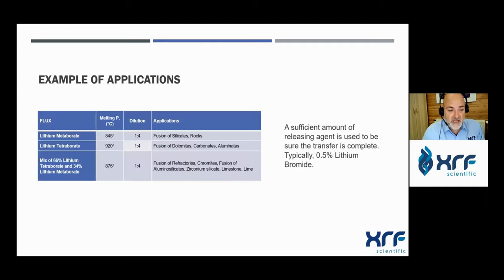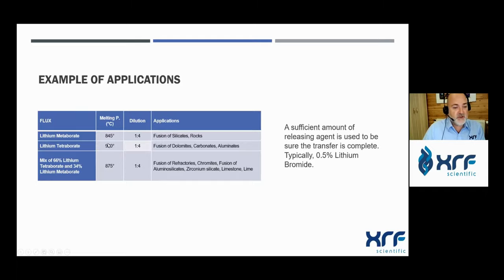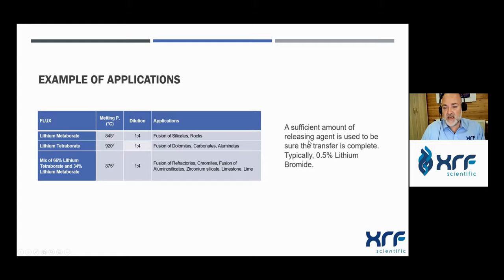The typical fluxes used are lithium metaborate, lithium tetraborate, or a mix of both, with different temperature ranges depending on the melting point of the flux composition. Dilution ratios are quite similar across all flux types. Typical applications include silicate rocks, dolomite, carbonates, and many other mineral products. In this type of fusion, a sufficient amount of lithium bromide must be added to ensure all product pours out of the crucible.